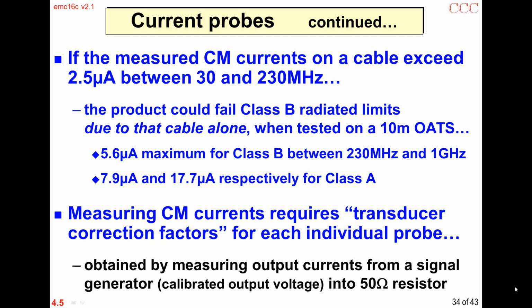Set the signal generator to a particular voltage and sweep through the frequency range, at various points like 100 kilohertz, 200 kilohertz, 1 megahertz, 3 megahertz, 10 megahertz, 30 megahertz, and so on. Plot what voltage you get out of the probe on your spectrum analyzer, with the 50 ohm termination, against the frequency. Since you know the voltage the signal generator is putting out, you know the current into the 50 ohm resistor, so you end up with a calibration chart for your probe.